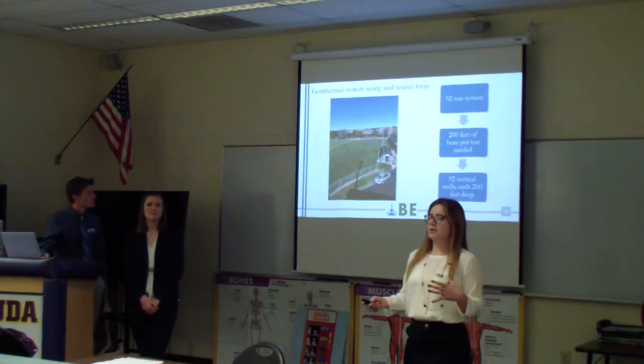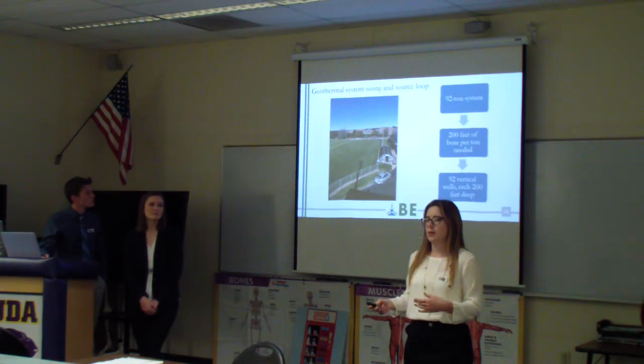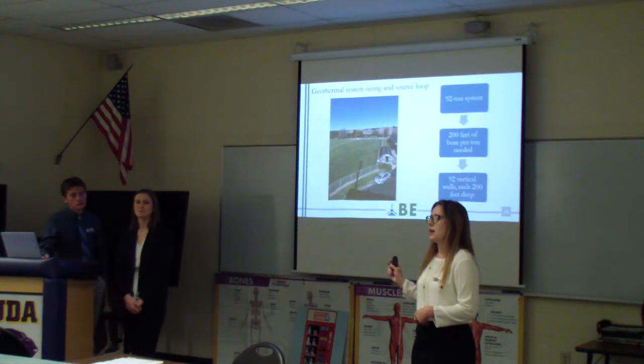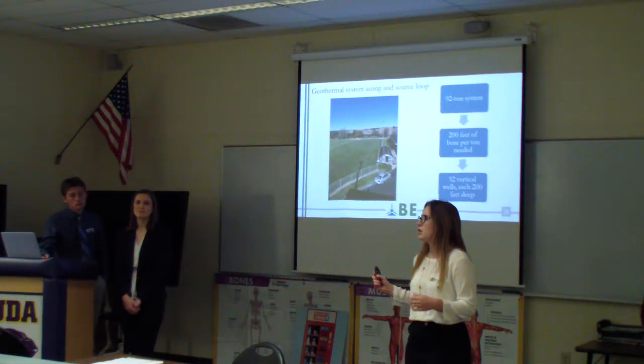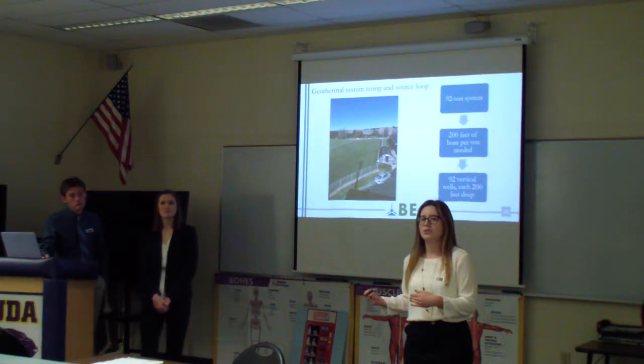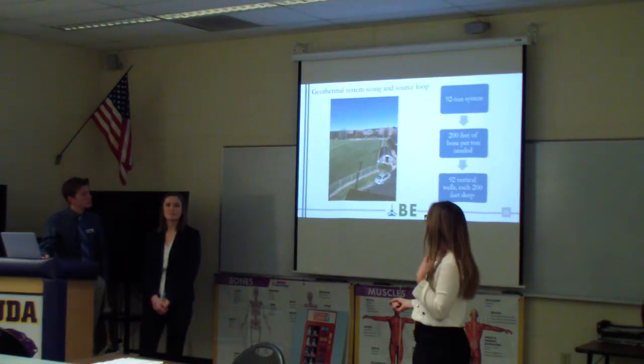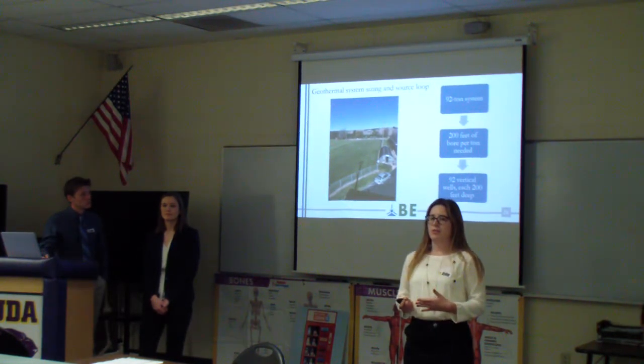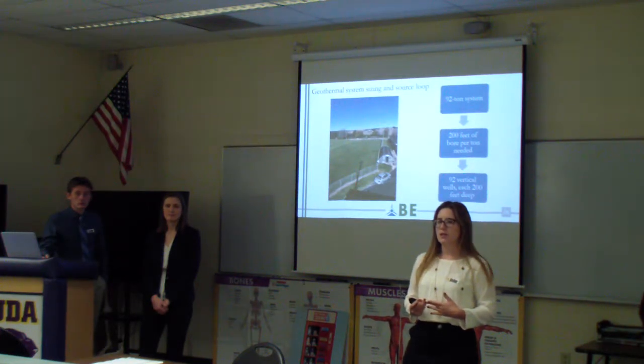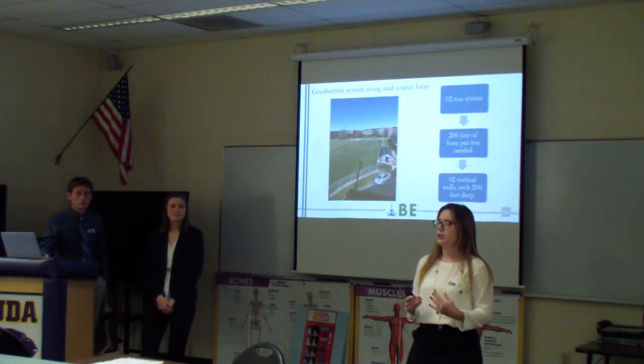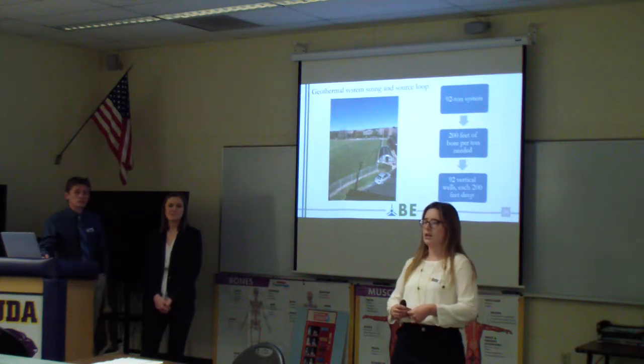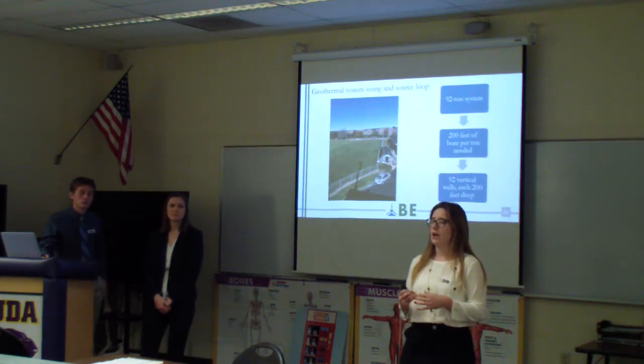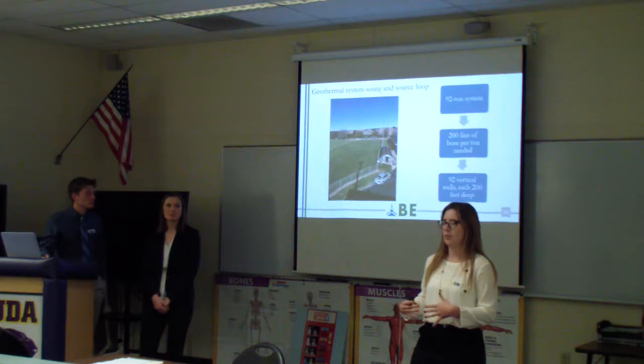So the next step is to design a source loop at Juda School. This is done by taking that peak month of natural gas usage and converting it to a number of tons. So for Juda School, you would need a 92-ton system. A good rule of thumb in a heating-dominated climate like southern Wisconsin is that you'll need 200 feet of bore per ton. So this means that Juda School will need about 18,400 feet of bore.